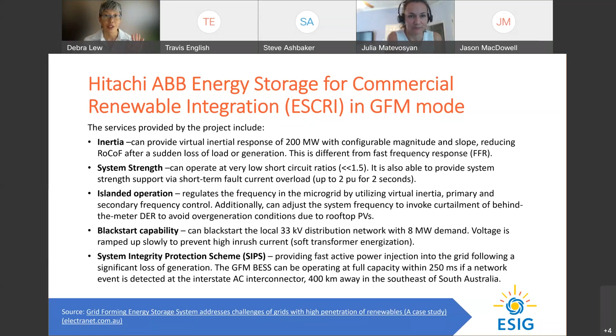And that's not very much related to this battery being grid forming. Grid following battery could have done this as well, but it's participating in the special protection scheme, where if interconnector from South Australia to the rest of the grid trips, and interconnector is 500 kilometers away, the battery will provide very fast frequency response to support isolated South Australian grid, to provide part of the support. It's not the entire scheme that they have there. Next slide, please. Julie, you've got 5 minutes left.